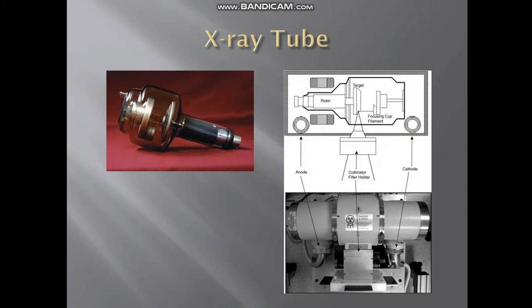This is for the fact that it is encapsulated inside the protective housing, which is responsible for reducing the level of leakage radiation as well as protecting the radiologic technologists and the patient from the risk of electrocution.